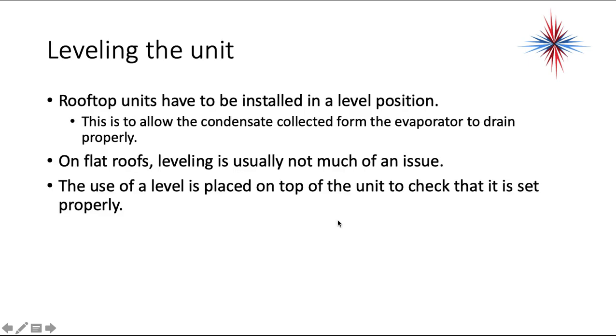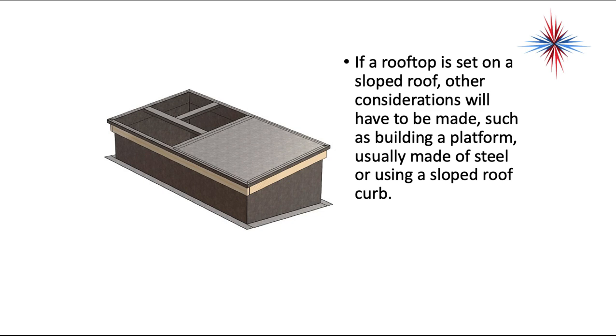Rooftop units must be installed in a level location. This allows the condensate collected from the evaporator to be drained properly. On flat roofs, leveling is usually not much of an issue. A level is placed on top of the unit to check if it's set properly. If a rooftop is set on a sloped roof, other considerations will have to be made, such as building a platform, usually made of steel, or using a sloped roof curb.